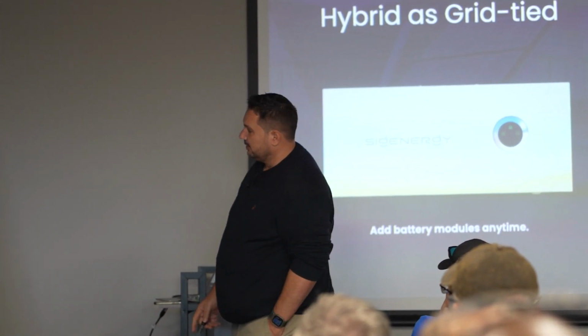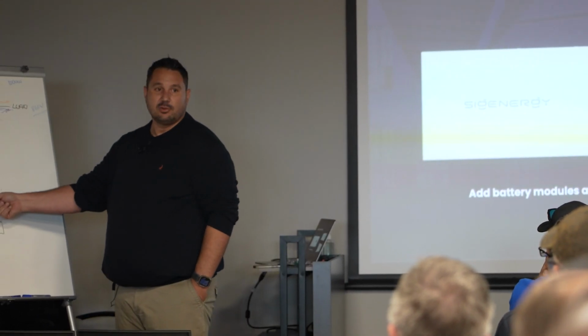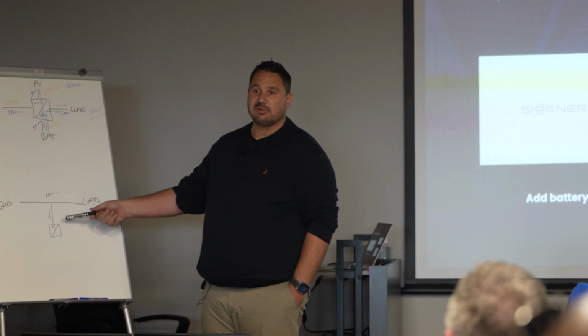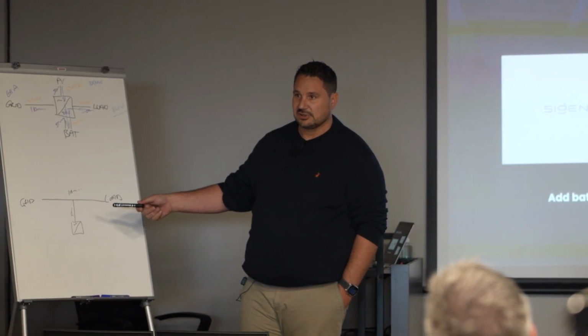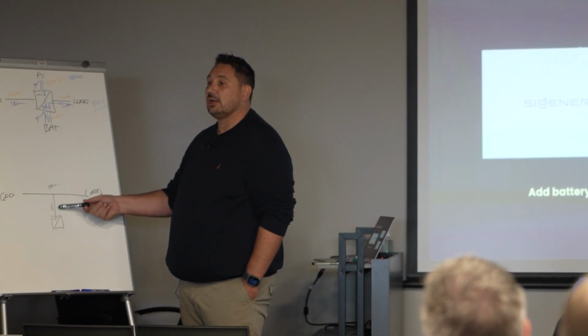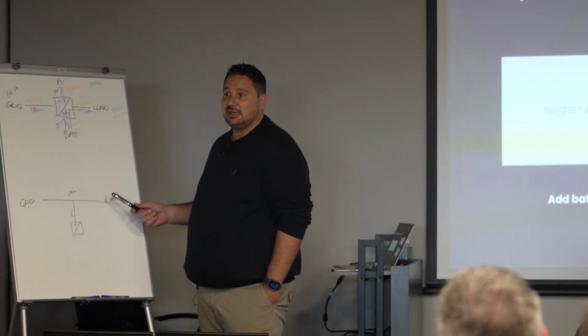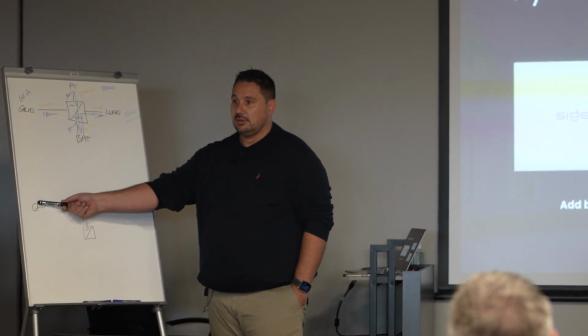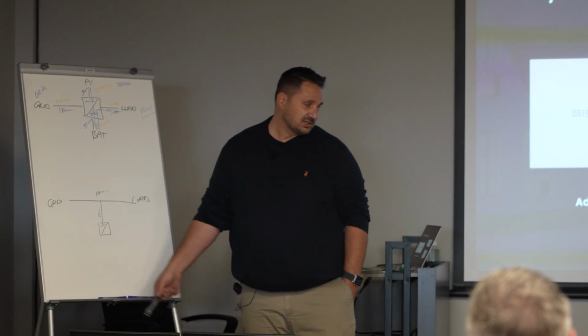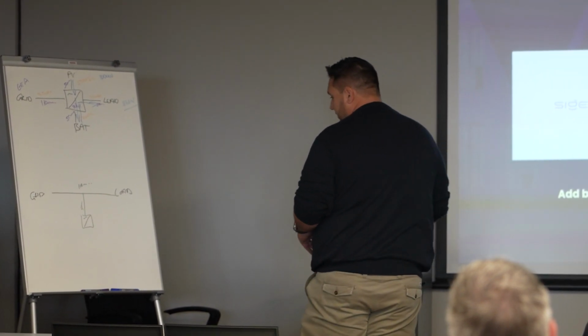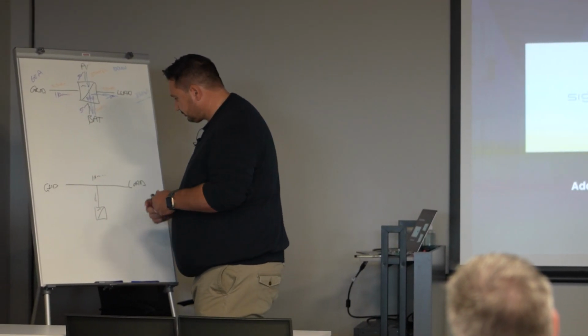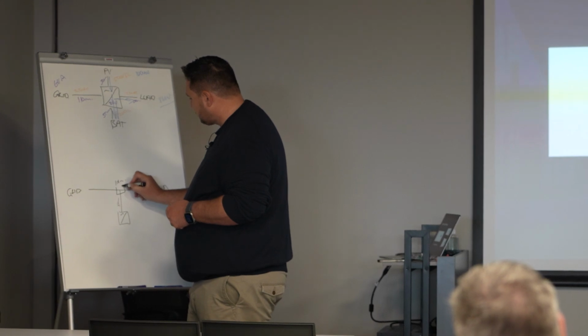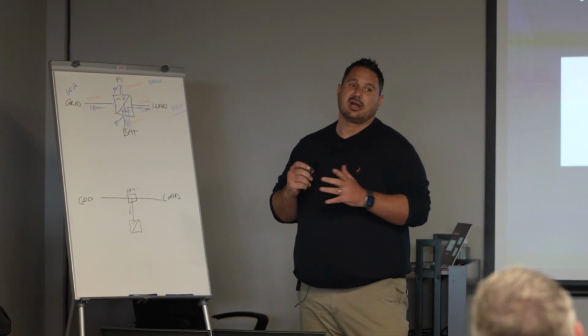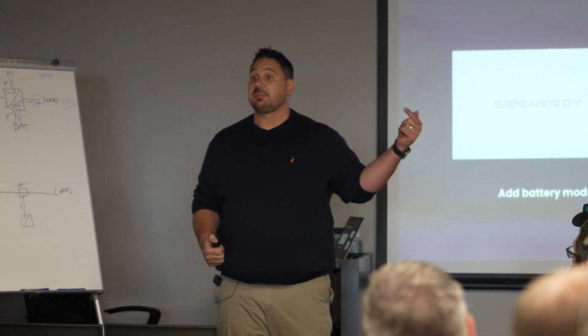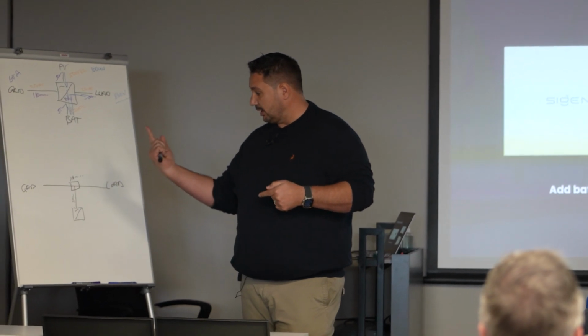160. Because we've got 110 from the grid and we've got another 50 coming in from the inverter side. Which means that your limit is actually, yeah, you can draw more than what is available from grid during sunlight hours. So the only thing that Sigenergy does is it basically puts a gateway in there. That's why that gateway's got a 100 amp breaker in it. So you can supply from the grid as well as from here.